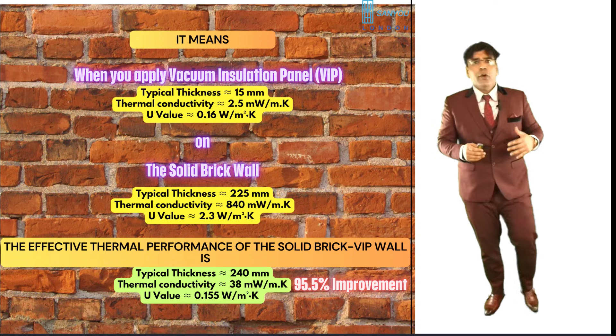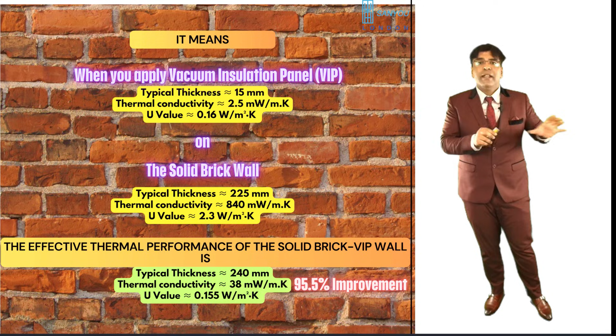If we were to look at the solid brick wall, it also means that when you apply the vacuum insulation panel to this solid brick wall, the effective thermal conductivity of the solid brick VIP wall is reduced from 840 to 38 milliwatt per meter per Kelvin. That's a 95.5% improvement, while the U value drops from 2.3 to 0.155 watt per meter square per Kelvin. This 95.5% improvement means that cooling or heating energy loss is reduced significantly compared to a standard solid brick wall.